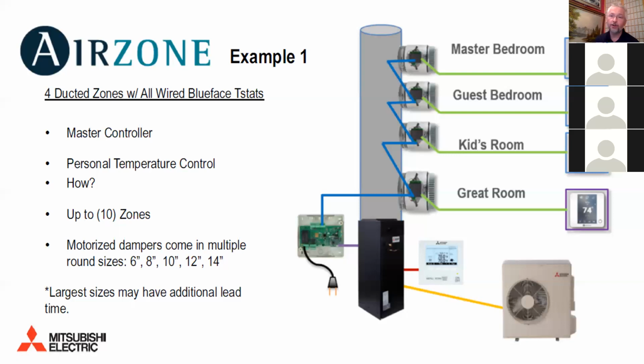And if you have to adjust any of the functions like static pressure, you need to have a Mitsubishi controller in order to adjust that. None of that functionality is incorporated into the AirZone tech. Okay, and then from the AirZone, there are 3 connectors on the top. They're all really one and the same. There's 3 of them just for convenience of connecting multiple wires, but they're all part of the same daisy chain wiring. And so then you run 4-strand shielded wire to all of the modules, whether they're ducted or other types of modules.